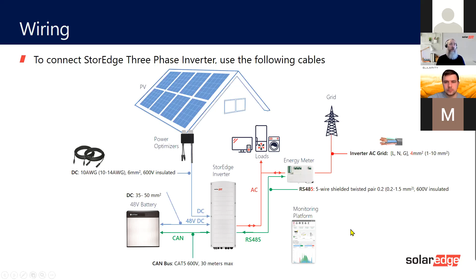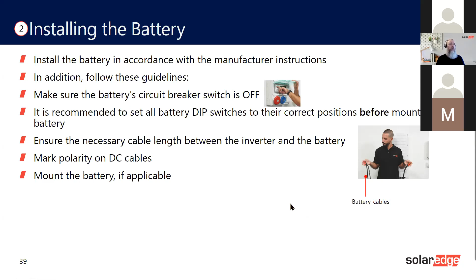Make sure that you set the battery dip switches before mounting the battery, and I'll show you where these are. Make sure the cables are the right length, no more than 5 meters for the DC to the battery, and mark the polarity on both ends of the positive cable. Unlike the PV array, which is in series (plus to minus), the battery connections are always plus to plus.